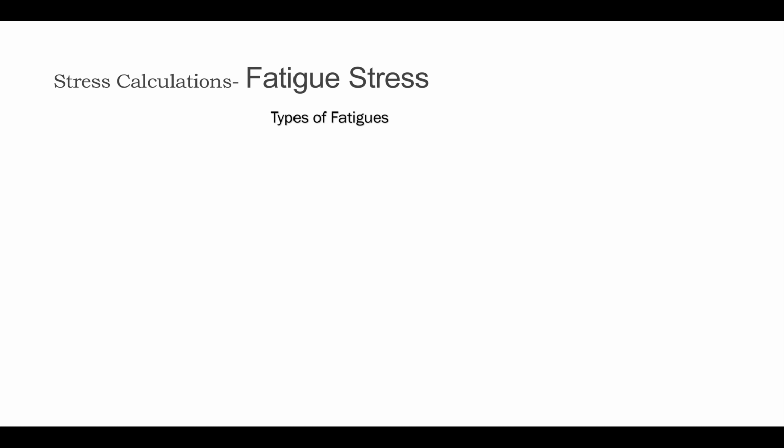This is very important. Fatigue is another type of stress in the piping system. As the pipes are in use, they experience repeated pressure fluctuations as well as temperature ramp ups and cool downs. These cyclic lives are a common metric for determining a pipe's lifespan, and they compromise pipe strength over time. So fatigue stresses are considered under secondary stress due to displacement driven loads. These are cyclic in nature and the mode of failure is fatigue.